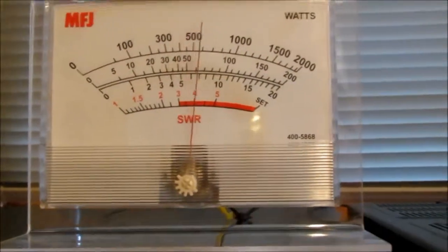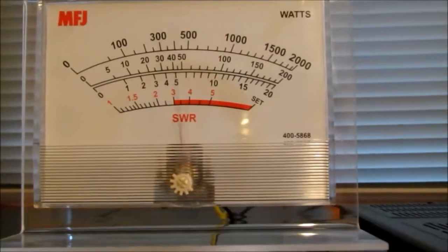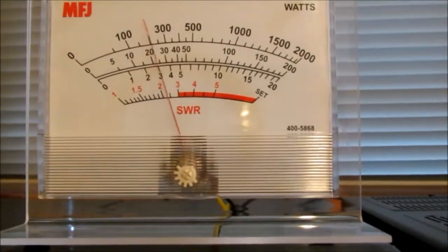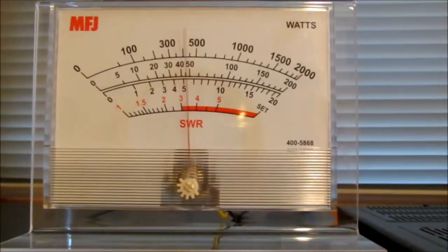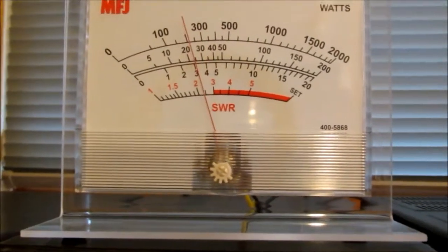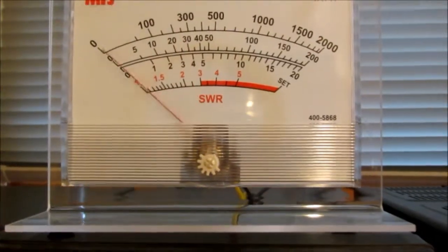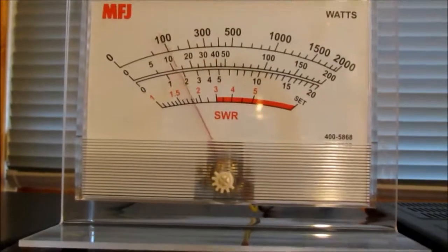So you can basically go into the simulator and pick the full scale option, which causes the meter to drive the output at what it thinks is the correct full scale reading. And at that point, all you have to do is adjust the trim pot so that the needle reads at the full scale reading, and all your other measurements will fall into place.